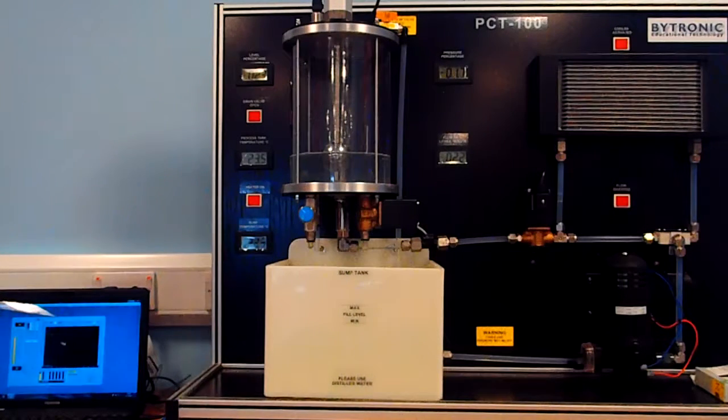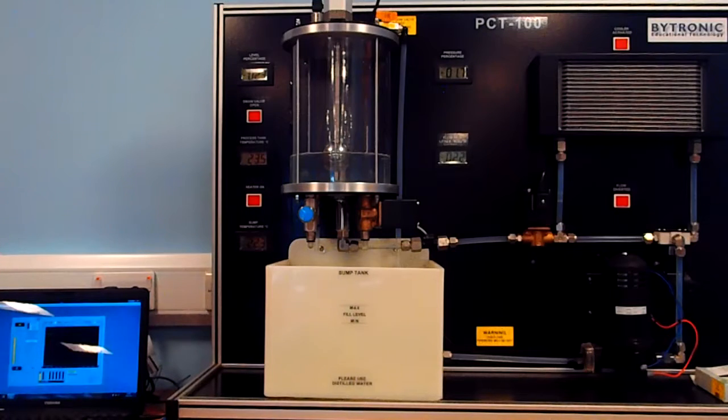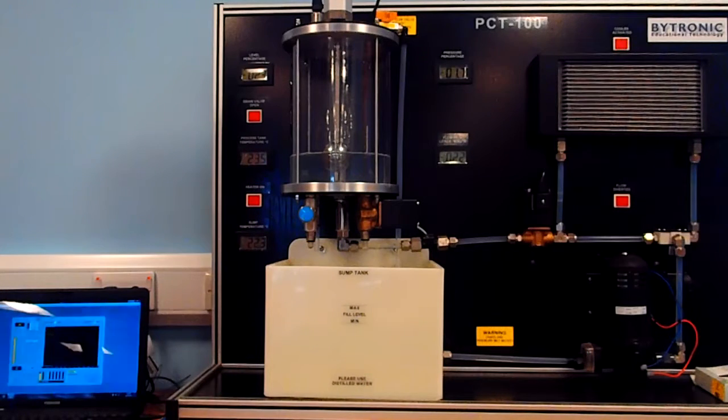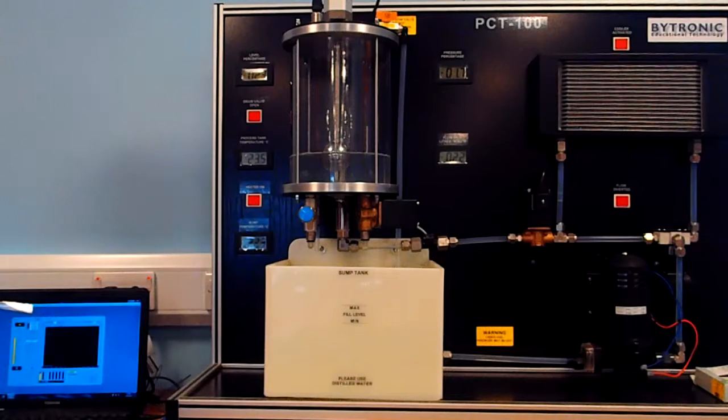The system's currently set up as an open loop control system. The loop has a proportional gain of 10, and that's just to try and speed the system up a little bit. You can see the yellow line here. I'm not sure how clearly you can see it. I'll maybe zoom in on that once I've showed you the system working. The yellow line here is our set point, or our reference input at 80%, and the blue line is our actual level measured by the float. So without further ado, I'll just switch it on for an automatic step change.